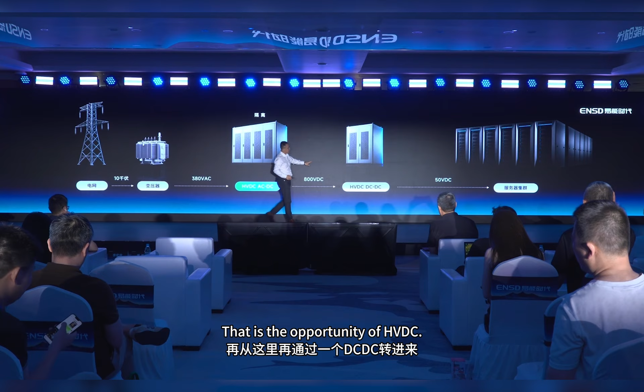Going one step further, the hot topic now is integrating HVDC with a transformer ahead of it. That is SST, or solid-state transformer. Put those together and you get a solid-state transformer. When solid-state transformers are fully deployed, power from the grid can go through a solid-state transformer and enter the server room directly. The path becomes extremely short, and the footprint drops dramatically.